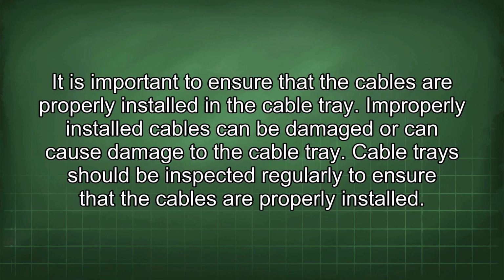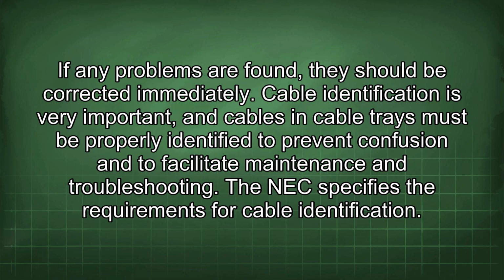It is important to ensure that the cables are properly installed in the cable tray. Improperly installed cables can be damaged or can cause damage to the cable tray. Cable trays should be inspected regularly to ensure that the cables are properly installed. If any problems are found, they should be corrected immediately. Cable identification is very important, and cables in cable trays must be properly identified to prevent confusion and to facilitate maintenance and troubleshooting. The NEC specifies the requirements for cable identification.